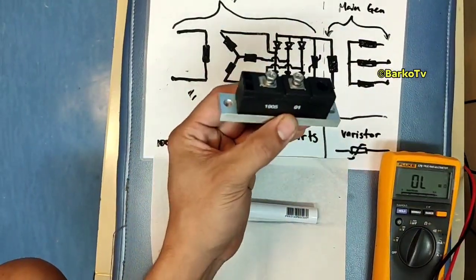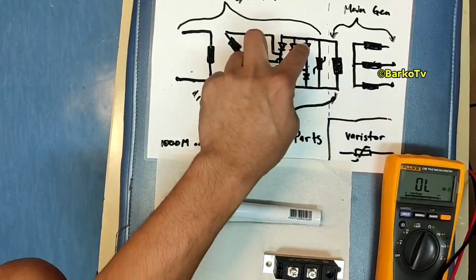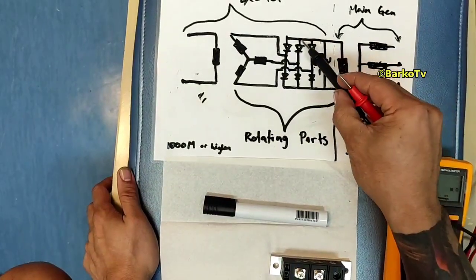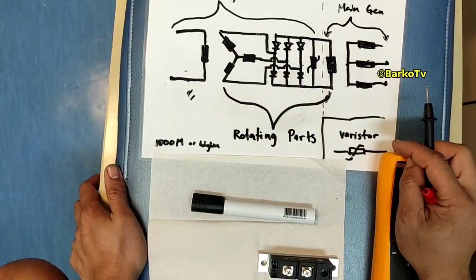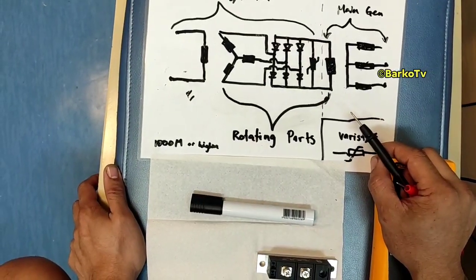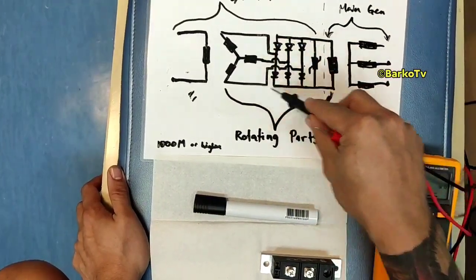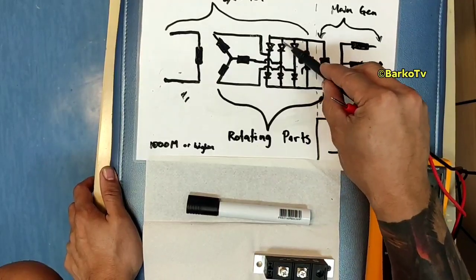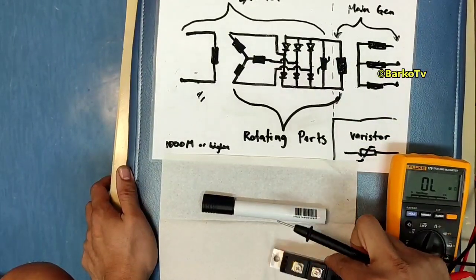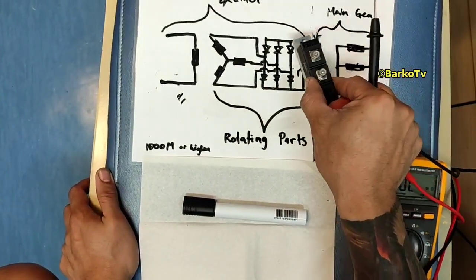What if this surge suppressor is removed from this circuit? This diode works or not? The answer is this diode is working fine, working good even though there is no surge suppressor. But if the time comes there is surge voltage coming to our exciter, this diode will damage. You need to put this - it is the protection for our exciter semiconductor parts.